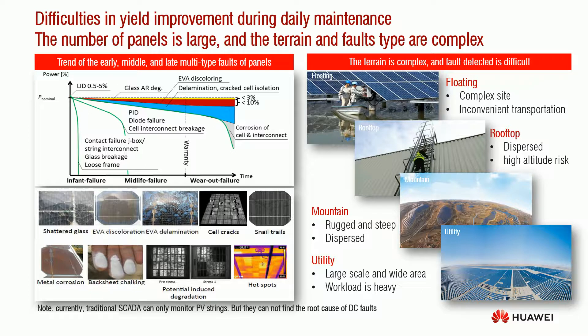The glass breakage, so-called shatter glass, is due to quality or environmental causes such as impact by a flying rock or material. Shatter glass not only has an impact on the output power of one module, but also causes the mismatch loss of strings containing this module. More importantly, the increased risk of safety occurs because the isolation level decreases largely when the glass is broken. It is easy to cause electrical shock on a rainy day or when water remains on the module surface. Therefore, when glass breakage happens, it is advised to replace the panel as soon as possible.